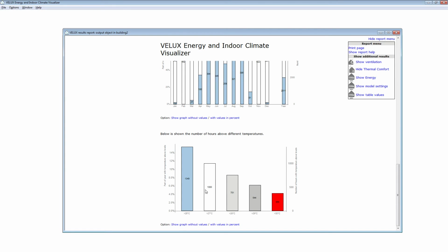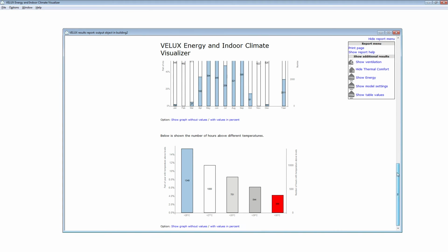And just to be completely clear, for residential buildings, we can't go beyond 100 hours for 27 degrees and 25 hours over 28. Therefore this apartment cannot be built.